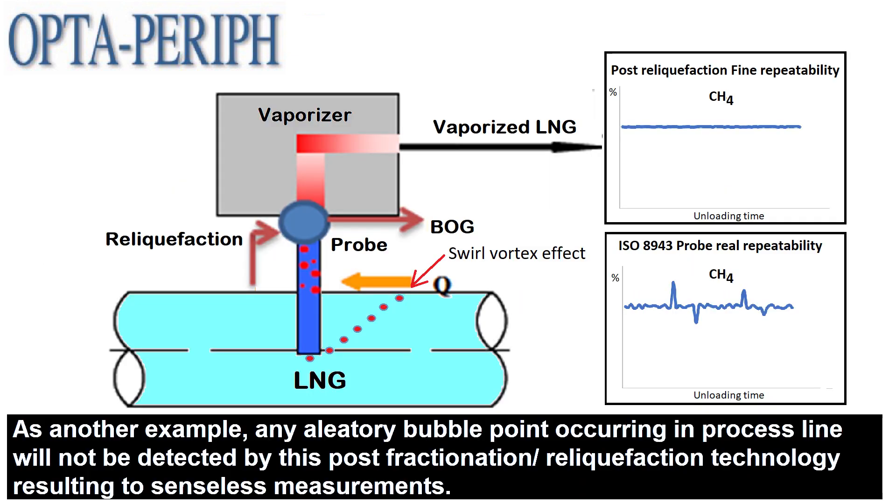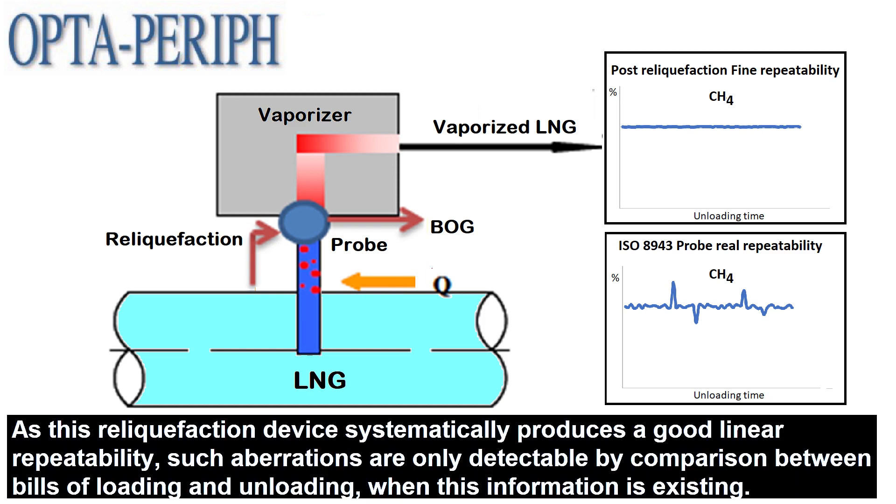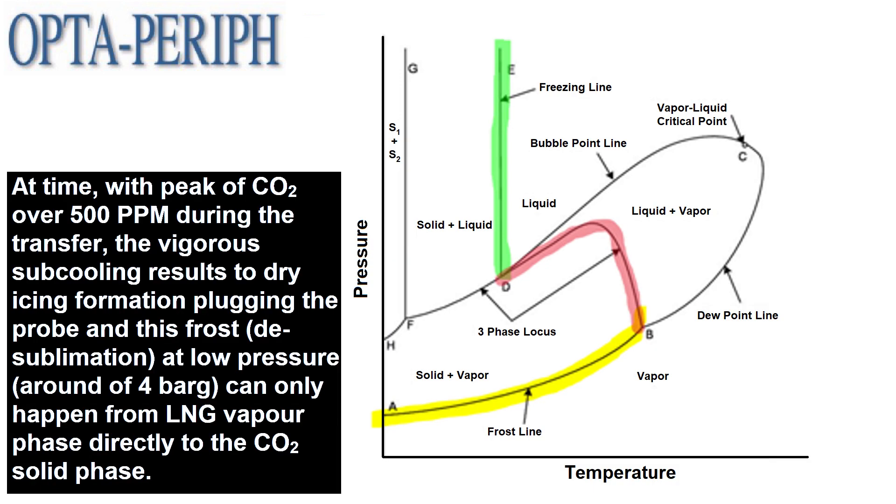As another example, any aleatory bubble point occurring in the process line will not be detected by this post-fractionation reliquefaction technology, resulting in senseless measurements. As this reliquefaction device systematically produces a good linear repeatability, such aberrations are only detectable by comparison between bills of loading and unloading when this information is existing.